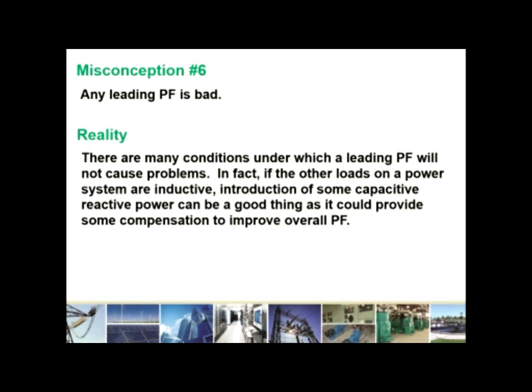And that leads us to the final misconception, which is just simply that any leading power factor is bad. I can't tell you how many times that I've heard that from various engineers, consultants, or other customer engineers concerned about the fact that they're measuring a leading power factor. But in reality, there are many conditions under which a leading power factor will not cause problems, and they've been covered in this presentation. So in fact, if the other loads on the power system are inductive, introducing some capacitive reactance can be a good thing, as it can provide some compensation to improve overall power factor.